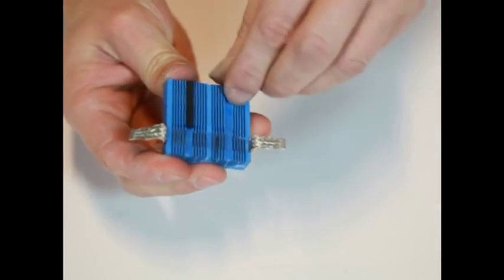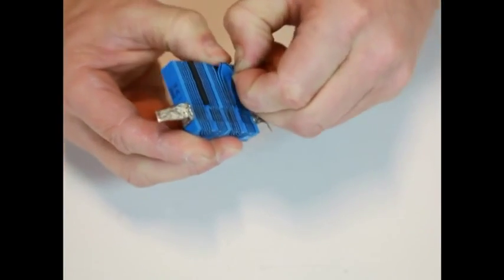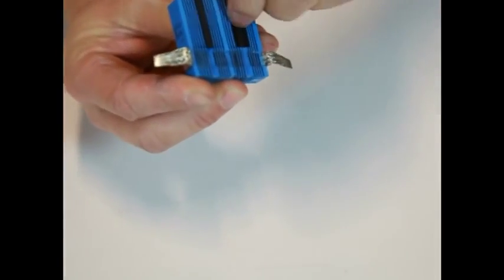Adapt outer layers to the cable or pipe diameter by peeling off layers from each module half. The halves must not differ by more than one layer.